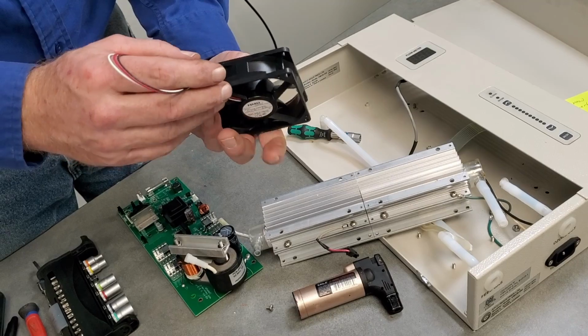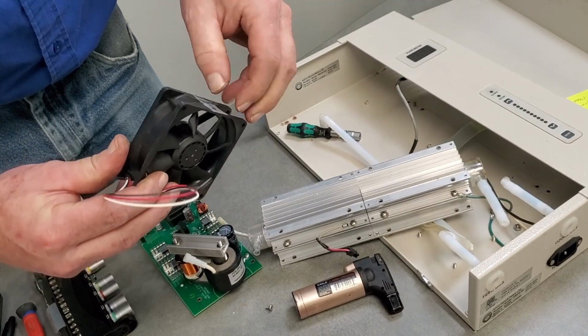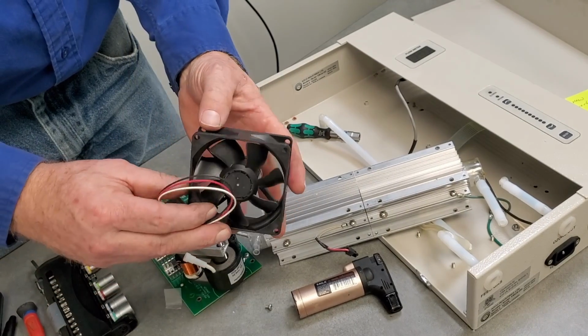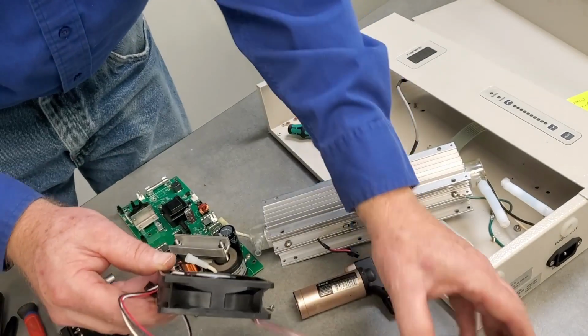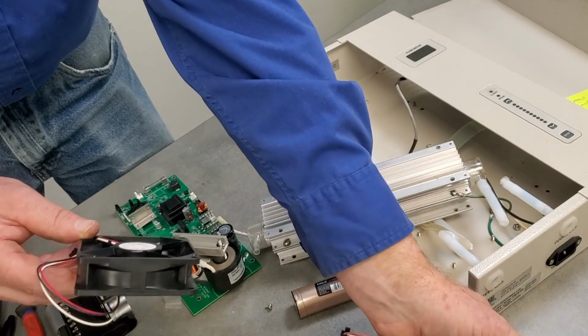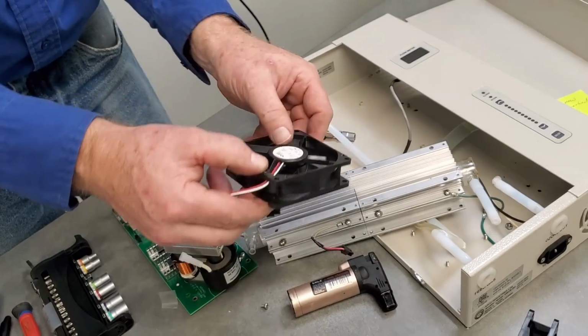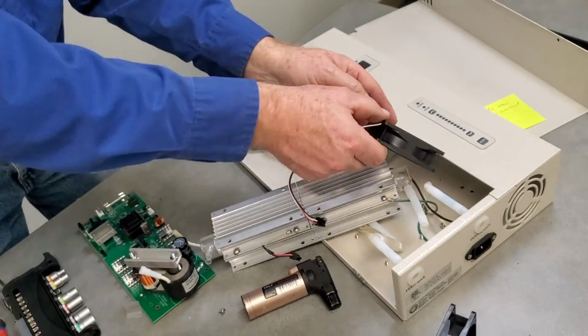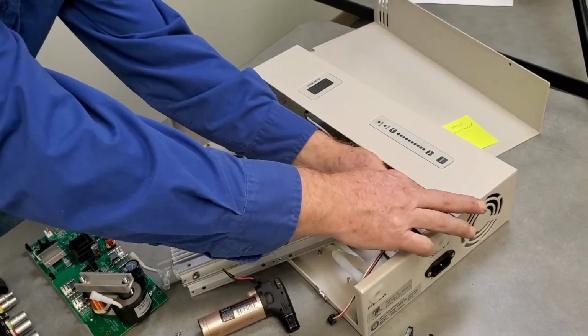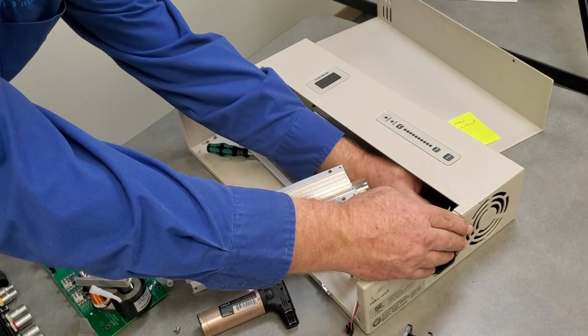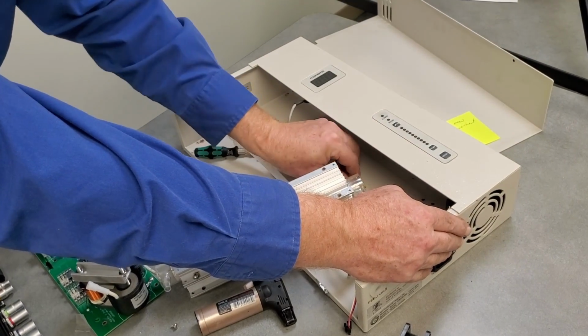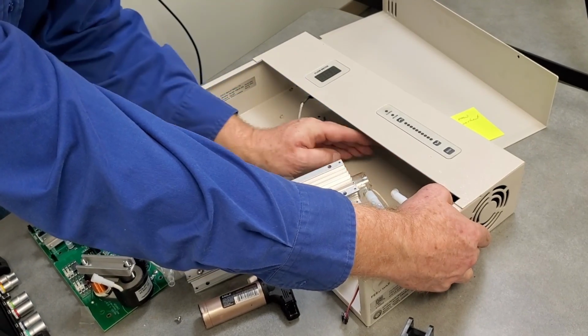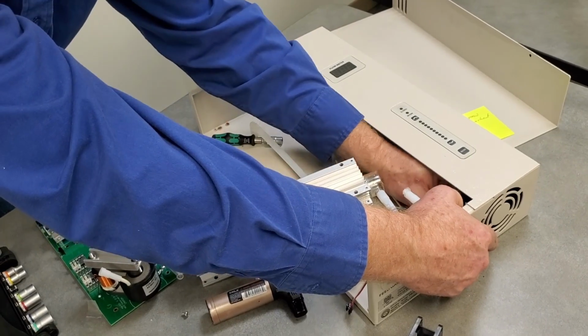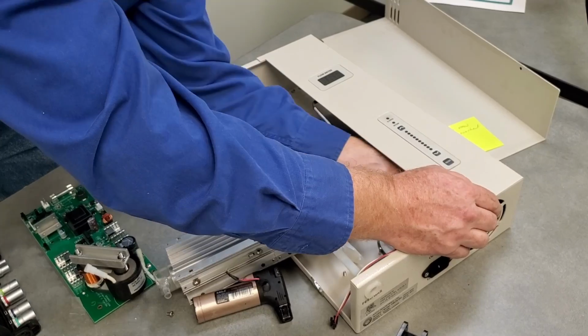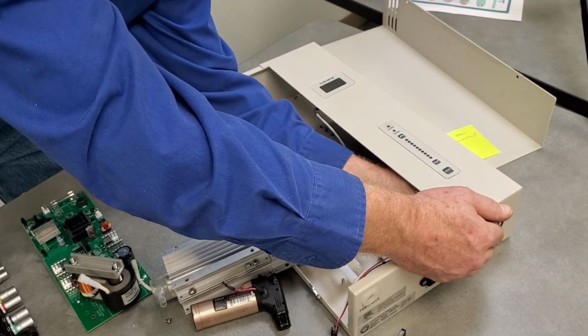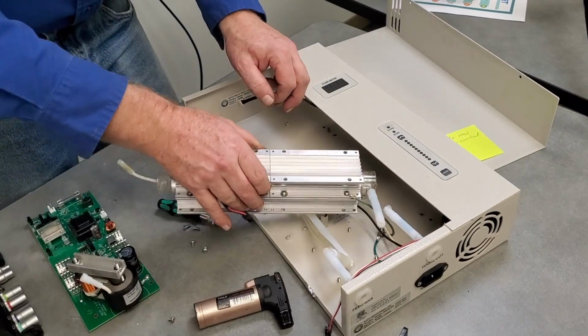Airflow needs to blow in. This one doesn't tell you which way it blows. About the fact that we've got some glue on there. All right, that's facing in, so we want to mount that one so that this little sticker is facing in. Two threaded studs in there that it has to slide onto, and then put the washer, the lock washer, and the nut. Okay, so our fan is in.